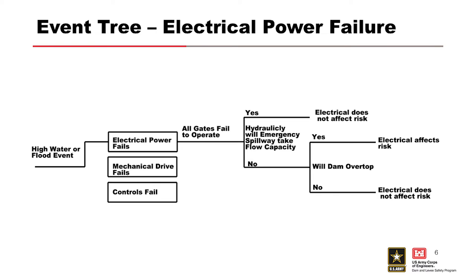This event tree steps through the events for an electrical failure that would potentially cause catastrophic failure. For electrical, typically, it's going to affect all gates on a project. A lot of times for electrical installations, there should be quite a bit of redundancy built in. You'll have two or three different sources of power. Commercial power, there may be a hydroelectric power source, emergency generator.